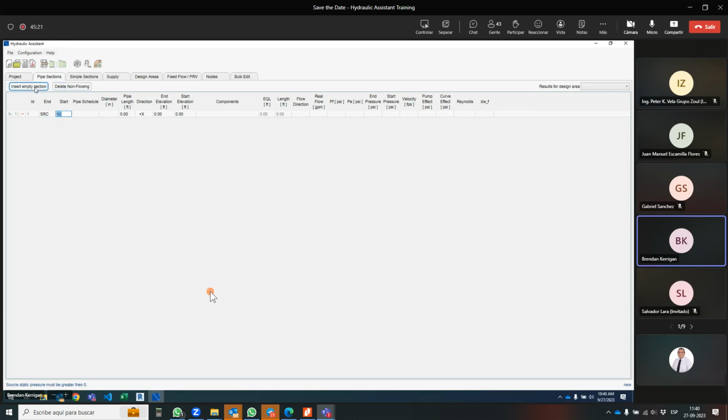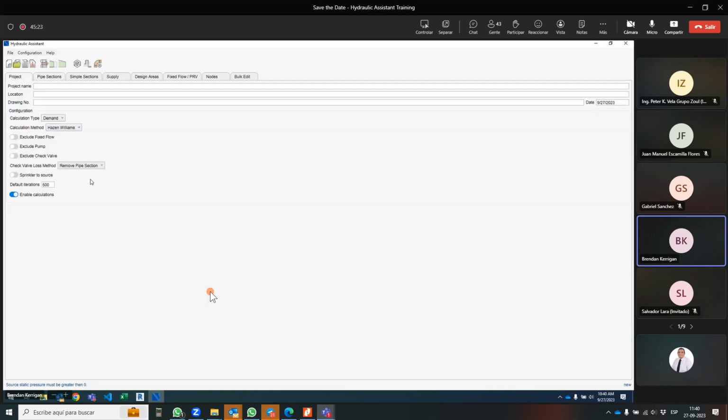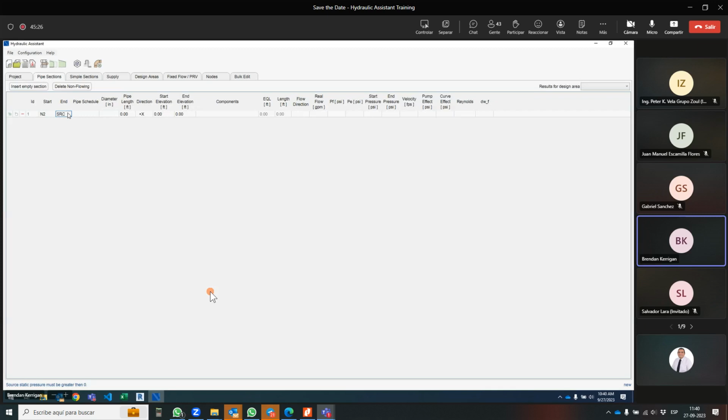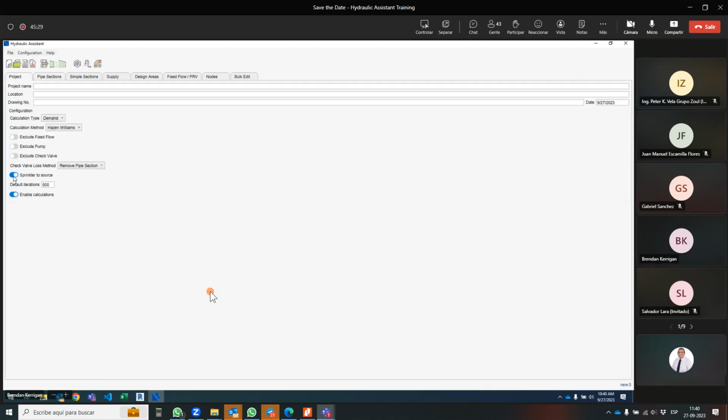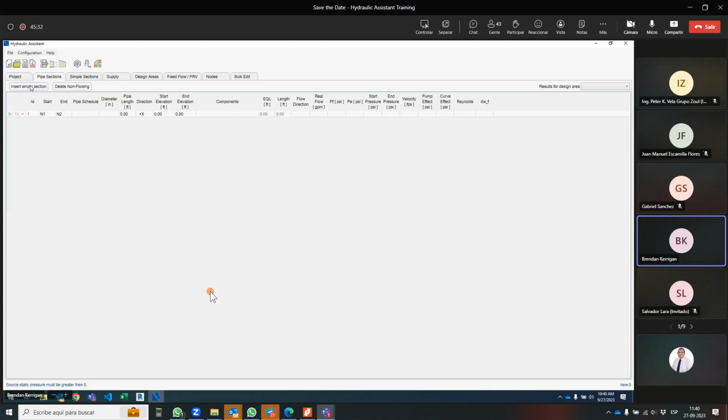Yeah, so if you want to do a standpipe calc, and for those, I actually also like to work my way, kind of start out. So here, let me just start a new project, turn that off. If you want to manually build out a pipe network in the standalone, you basically got to build a big table here that you can work your way through. Same ideas within the Revit model. You can provide the name of the start node, the end node, come along, pick a pipe schedule, pick a pipe diameter, so maybe it's 4 inches, 10 feet long, give it some elevations, maybe it's got an elbow on it or something. You can come in and you can hand key this information in.